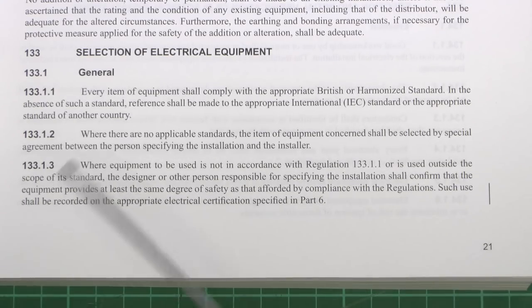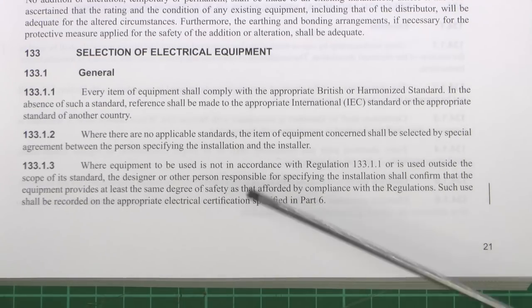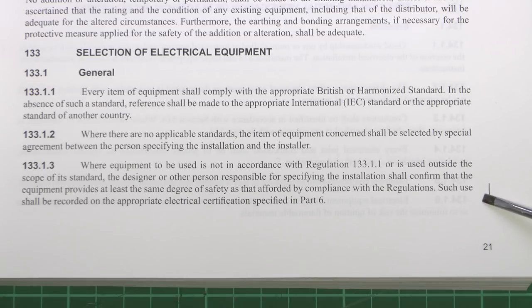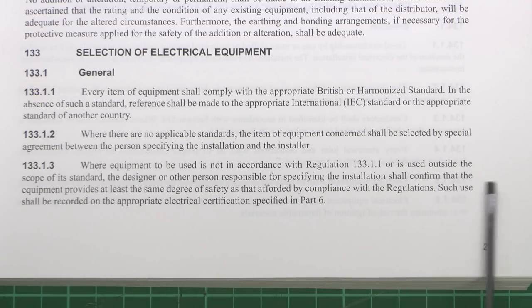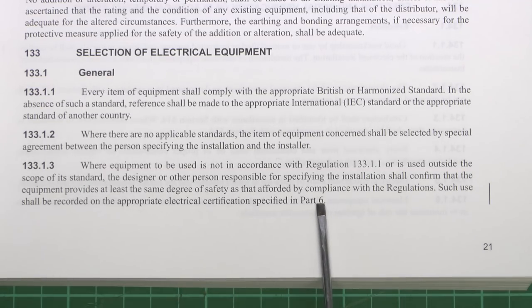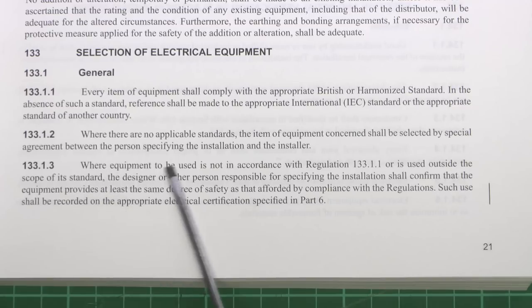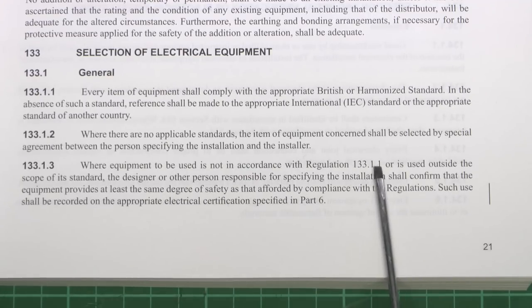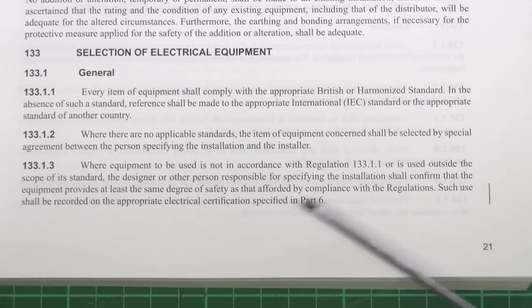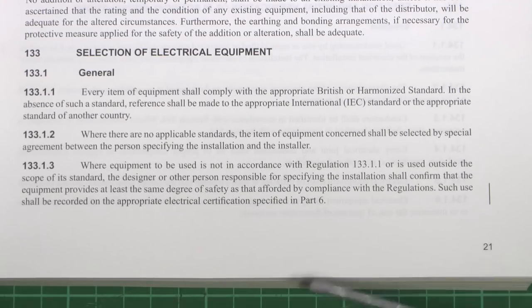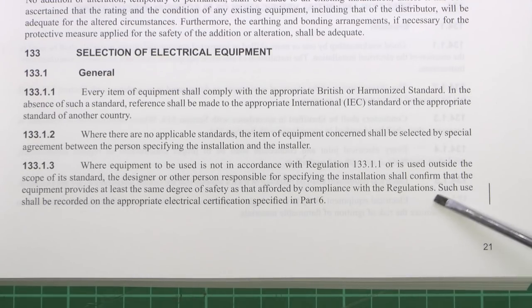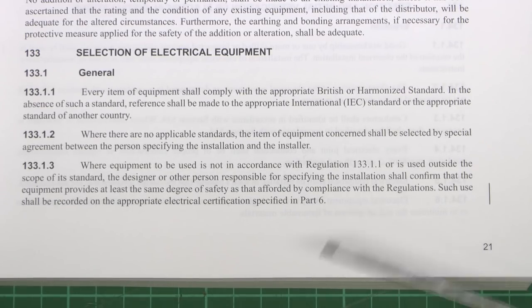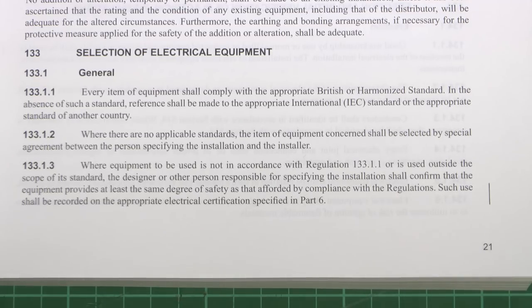The final item of relevance in Part 1 is Regulation 133.1.3. The part that's been added is: 'such use shall be recorded on the appropriate electrical certification specified in Part 6.' This regards where equipment is to be used not in accordance with this regulation, or is used outside the scope of its standard, but it is confirmed that the equipment is at least the same degree of safety as that afforded by compliance with the regulations. So the only difference is now it needs to be recorded on the appropriate electrical certificate, whereas previously it didn't actually require that.